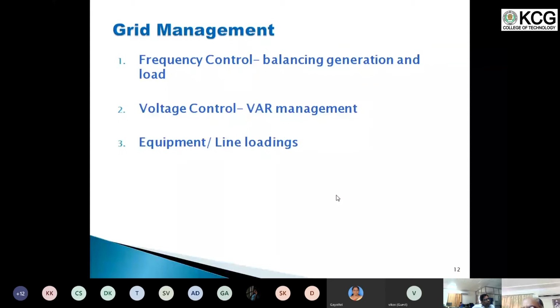Also, from the angular stability point of view, there will be limitations on line loadings, and the transformers, based on their MVA rating, will have loadability limits, and these need to be honored. Otherwise, if you overload them, you lose their life, and if you overload them too much, maybe they trip out, which will create more problems. If one transformer trips, then the other elements in the system will need to share that power flow, and then they can get overloaded. So the grid operator has to see to it that the equipment and lines are not going beyond their normal loadings.